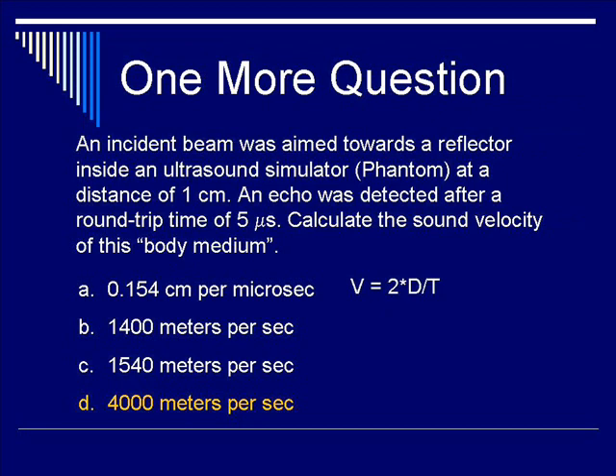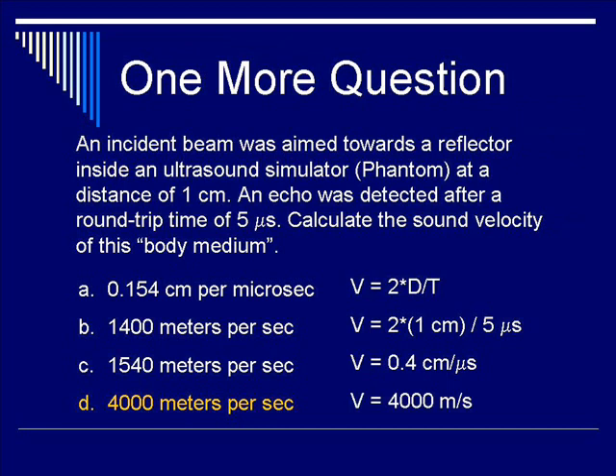The correct answer is D, 4000 meters per second — right away you know this is probably bone. Using V equals 2 times D divided by T, plug in distance of 1 centimeter and round trip time of 5 microseconds. You get a velocity of 0.4 centimeters per microsecond, which translates to 4000 meters per second. This phantom is most likely simulating sound travel in a bony medium.